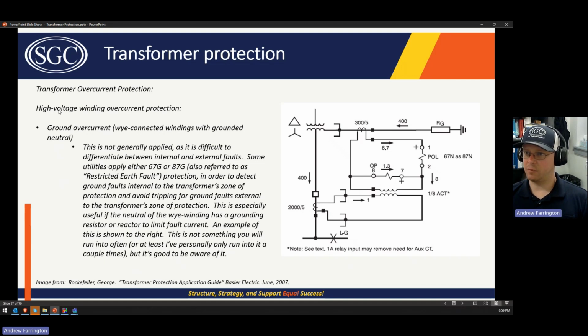If the high voltage winding is a Y grounded connection, typically you don't want to set an instantaneous element, because if there are other lines off of this bus, this is the high voltage winding in this case, there's no way to differentiate between a close-in fault on this line or a fault on the bus or a fault in the transformer. Those would all have basically the same amount of fault current. So you don't want to set an instantaneous element, unless you do something like restricted earth fault, which is often or sometimes referred to as a 67G or an 87G element.